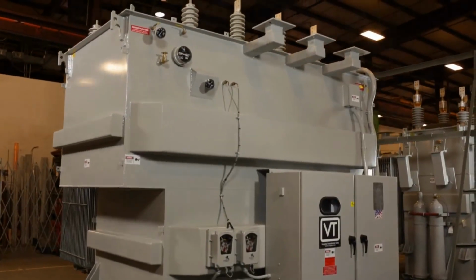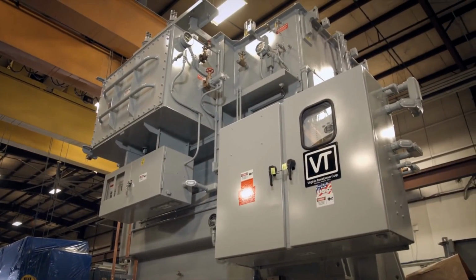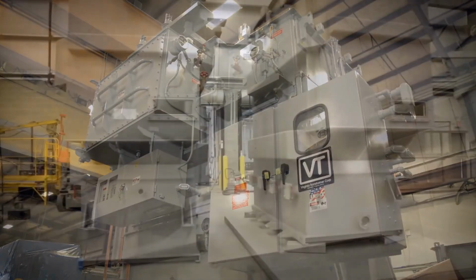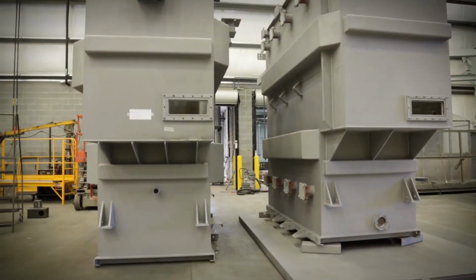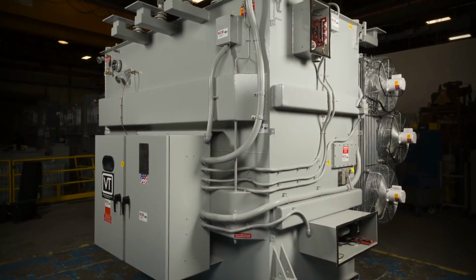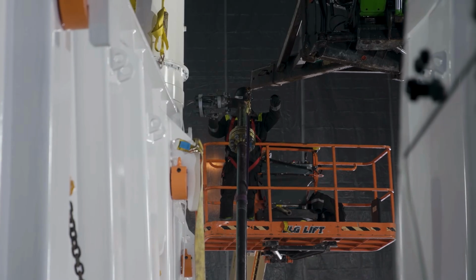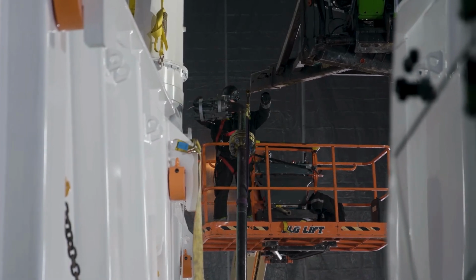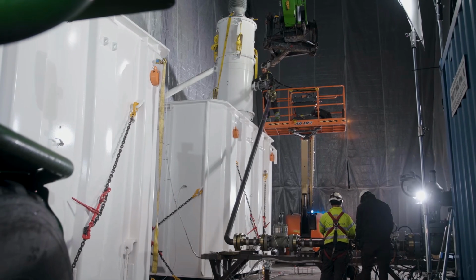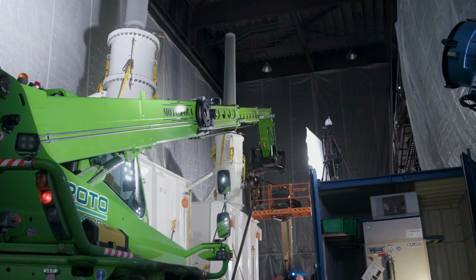Winding is followed by core and coil assembly. Large components have to be lifted, aligned, compressed, connected, and placed inside the tank. Insulation and internal clearances have to remain controlled through every step. The assembled unit then goes through drying, oil processing, and other preparation before it can be shipped.